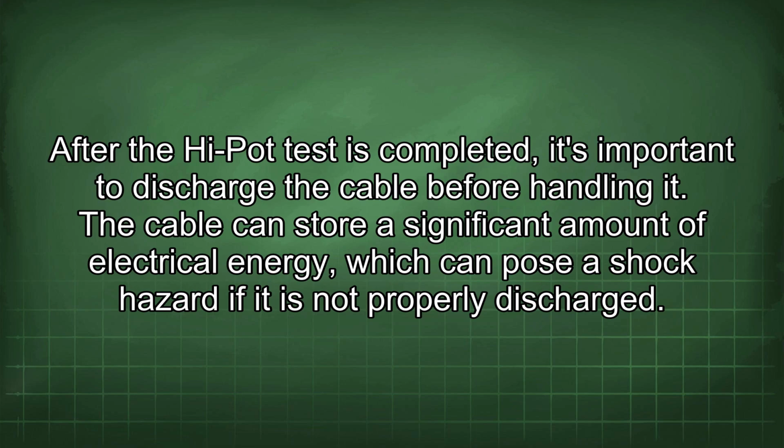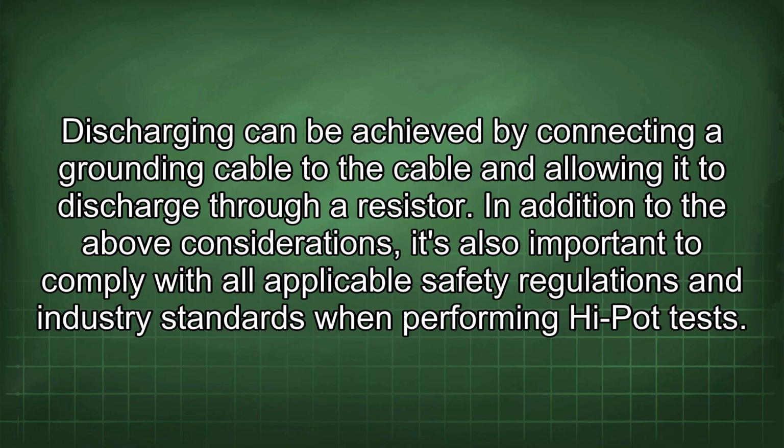The cable can store a significant amount of electrical energy, which can pose a shock hazard if it is not properly discharged. Discharging can be achieved by connecting a grounding cable to the cable and allowing it to discharge through a resistor.